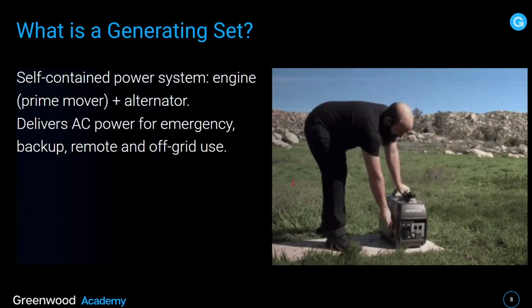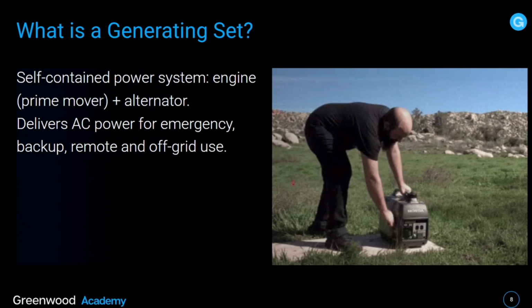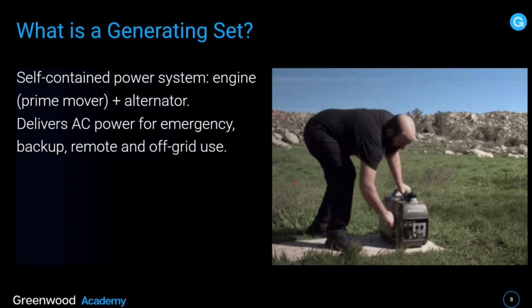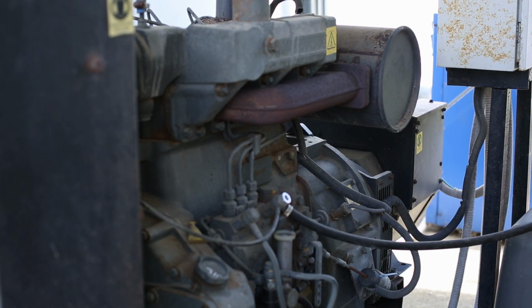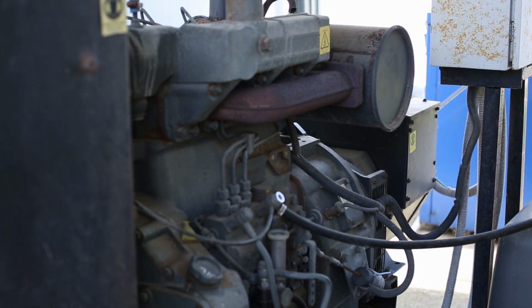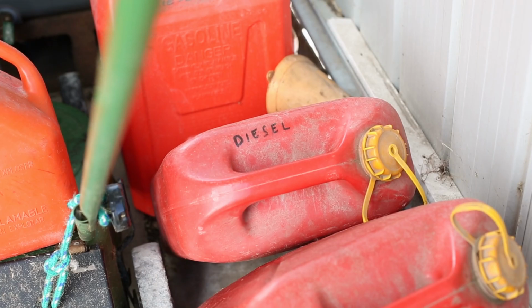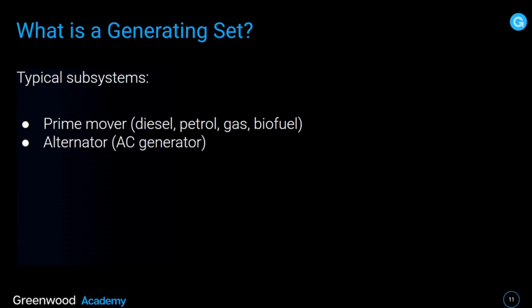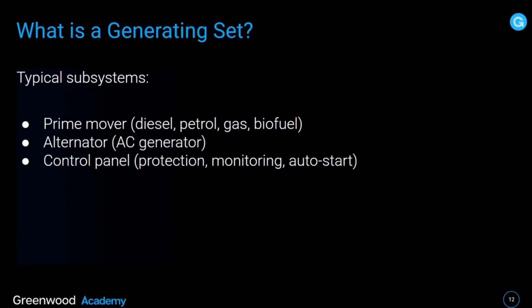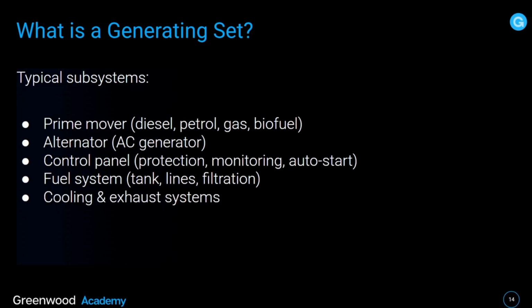What is a GENSET? Effectively, it's a self-contained power system, engine and alternator. It delivers AC power for emergency backup, remote and off-grid use. Now, typical subsystems include prime mover, which is either diesel, petrol, gas or biofuel, the alternator, which is the AC generator, the control panel, protection, monitoring and the auto start, fuel system, tank lines, filtration, cooling and exhaust systems, base frame, the skid and the vibration isolation.